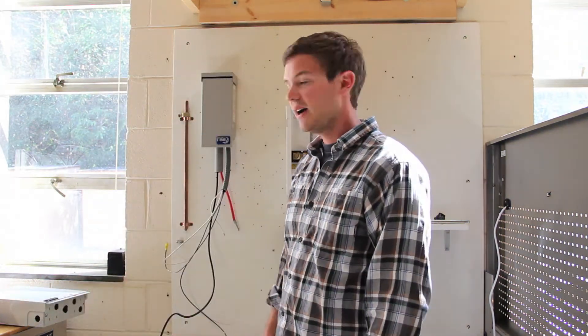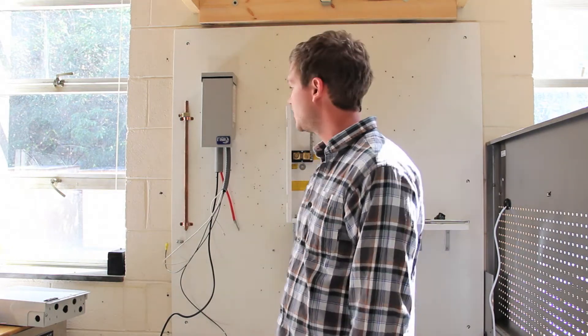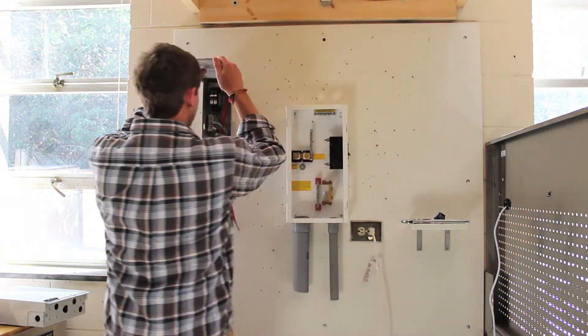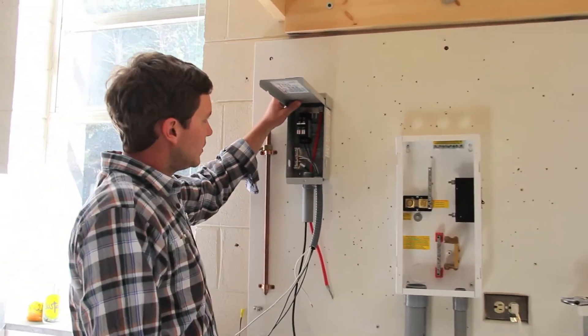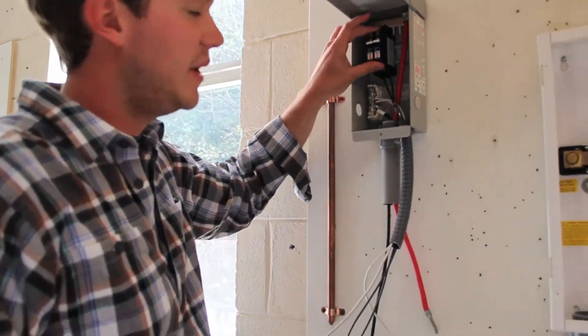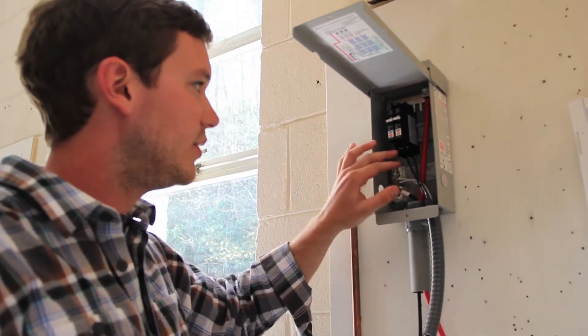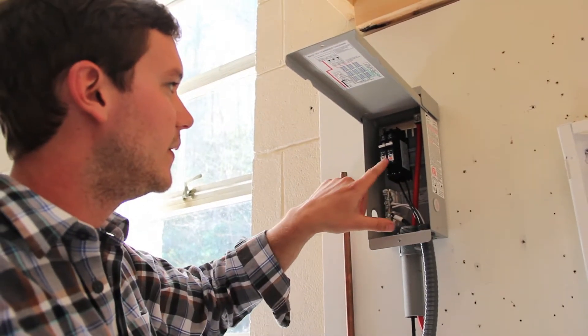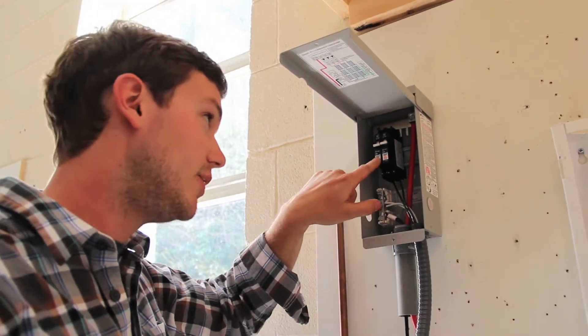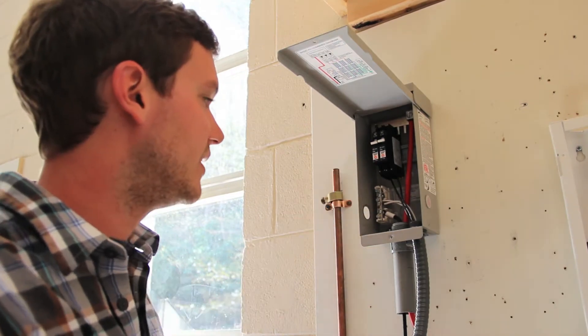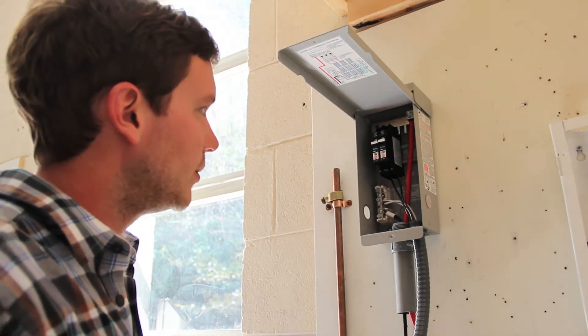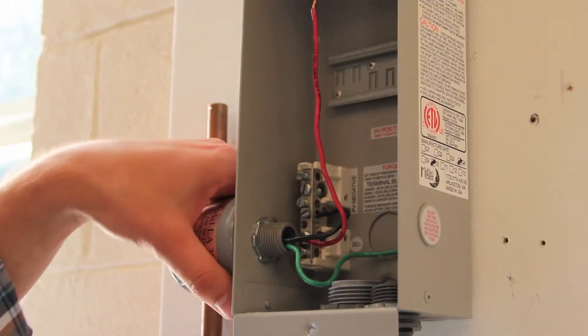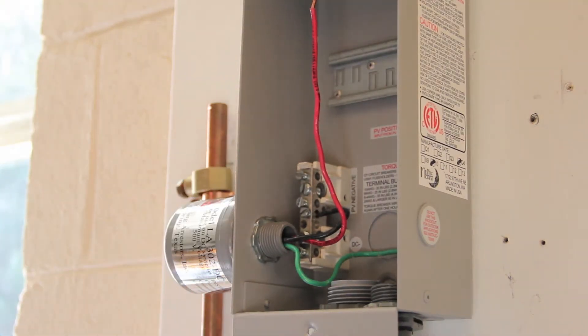For small systems and at Appalachian State, we use the Midnight Solar MN PV3 combiner box. This combiner box allows for the parallel combination of up to three strings of photovoltaic power. These breakers are rated to 150 volts, so it may not be appropriate for high voltage grid tie systems, but for lower voltage systems, a combiner box like this works great. This is our Midnight MN PV3 combiner box.